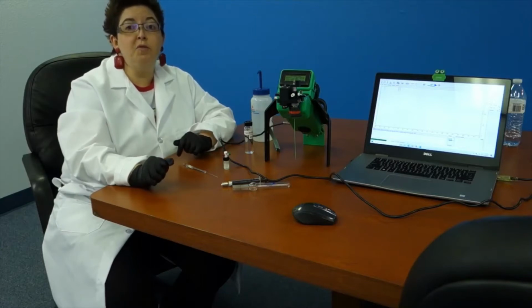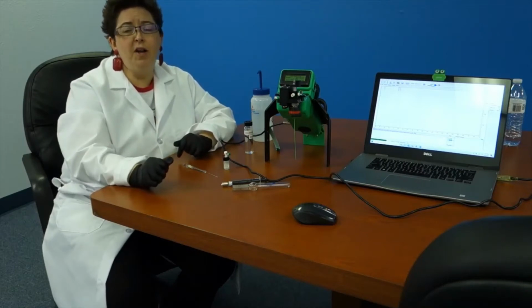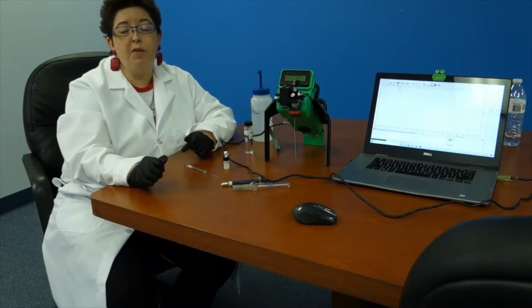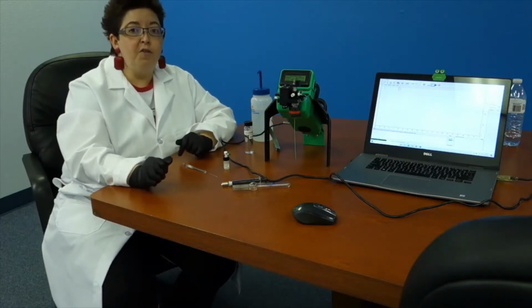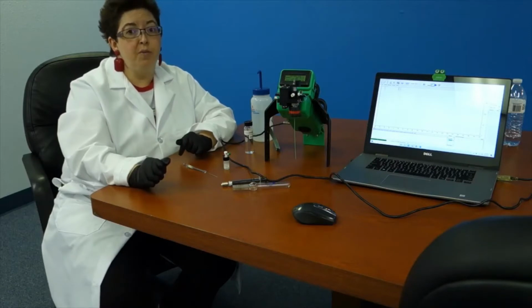For the purpose of our demonstration, we're going to be doing a calibration with water. Okay, a water calibration can be used for groundwater or can also be used for soil. Okay, the basic process, however, for air is not any different. You're just going to be doing samples with air. Simple as that. The very first thing that you want to do is run a blank.